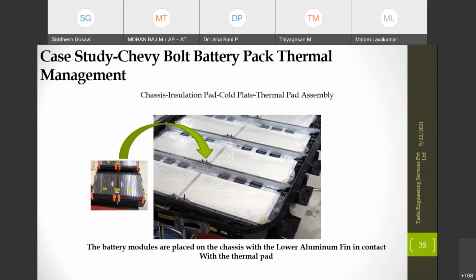Like we have discussed, the temperature gradient in the cell, intracell and intercell, is one aspect. But if there is a temperature gradient within my cold plate itself, then that becomes a problem at the source itself. Say for example, if my temperature here is 15 degrees Celsius, and at the corners or the surrounding region, it is 20 to 23 degrees Celsius. If there is a problem at the source cold plate itself, then this problem shall be reflected in my cell temperature gradients.